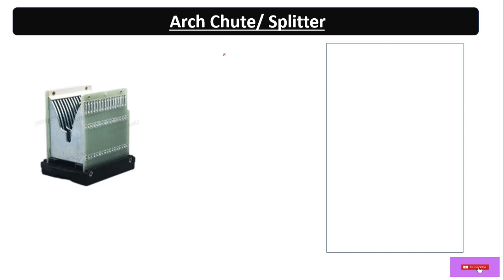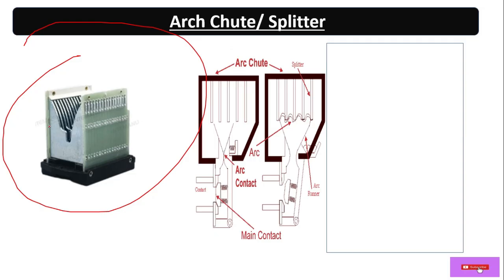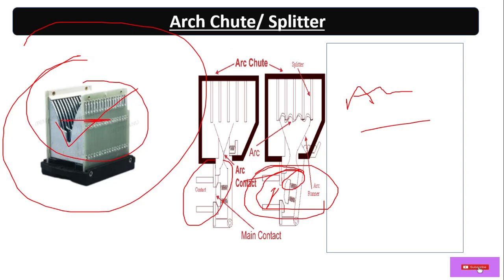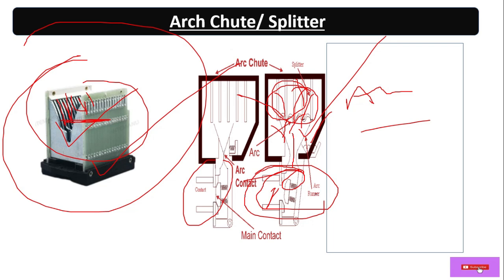The arc chute and arc splitter: during the opening of the circuit in case of any fault, when the contacts break, an arc is generated — basically fire is generated. ACB stands for Air Circuit Breaker, so air is the arc quenching medium. As you can see, these are metal plates — through the splitter the arc is divided, distributed, and extinguished. This is the arc chute which splits and extinguishes the arc.